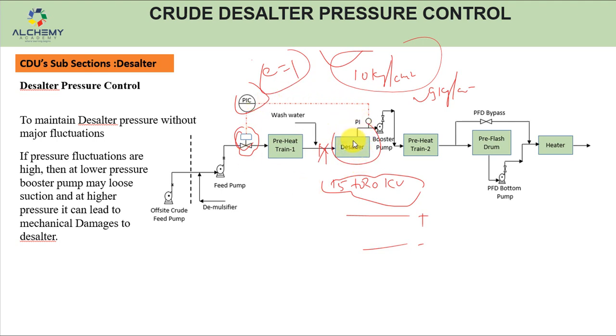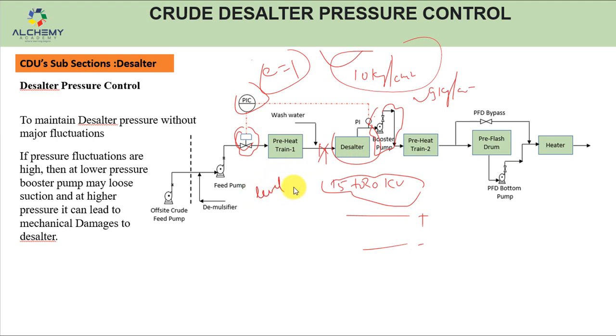If we don't control the desalter pressure, high pressure fluctuations can cause the booster pump to lose suction at lower pressure. At higher pressure, it can lead to mechanical damage to equipment — if excessive pressure reaches the desalter, the internals can be damaged. So that covers the control philosophy of the desalter: level control and pressure control. That's all for today — if you have any doubts, please comment in the comment box and I will try to clarify. Thank you so much.